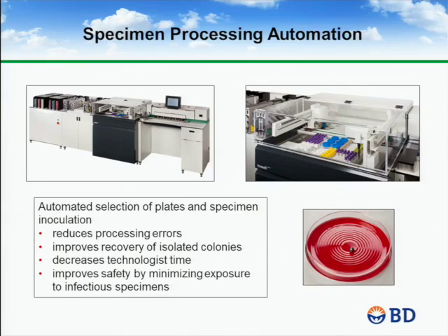And so, as you can imagine, you can change that streaking pattern in any way that you want, including, I guess if you're so inclined, you can have the technologist initial the plate when they get done. But what this allows you to do is it reduces the processing errors, it improves the recovery of organisms because you have well-isolated colonies, decreases the technologist time because they're not doing this, the instruments are doing these types of functions, and it improves safety because you're not exposed to aerosols that are created by our traditional procedures.